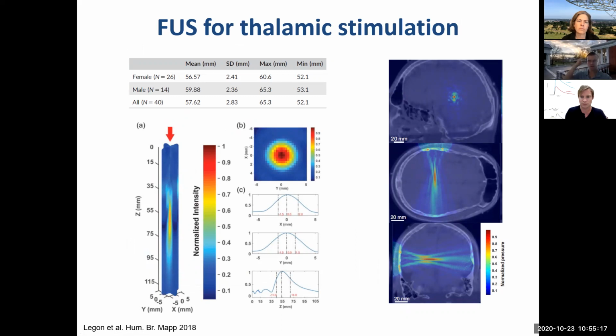And so we decided to target the thalamus through the side of the head. I mean, technically you could go from anywhere in the head, but the side of the head is advantageous because the bones are thinner and flatter. And this was the shortest distance to the thalamus. Here are the average numbers for all our subjects. We had 40 subjects, and our target was on average 57 millimeters from the scalp surface. So then we developed a transducer that had its field at that depth.